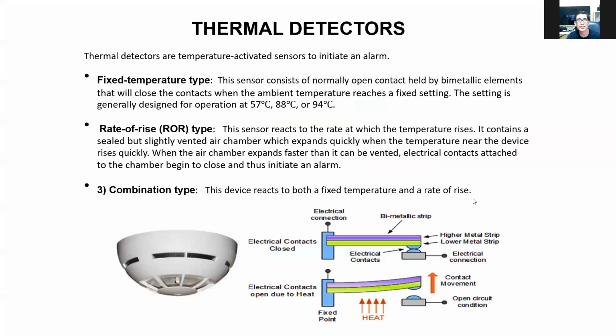So we have the thermal detector: fixed, rate of rise, and the combination. For the fixed type, the sensor consists of a normally open contact held by thermally sensitive elements which close the contacts when the ambient temperature reaches a fixed setting. The setting is generally designed for operation at 57 degrees centigrade or 94 degrees centigrade. So that is very hot. 57 is very hot. 38 is hot, like if you have a fever, that's 38. So if it's about 57, it's almost flame.